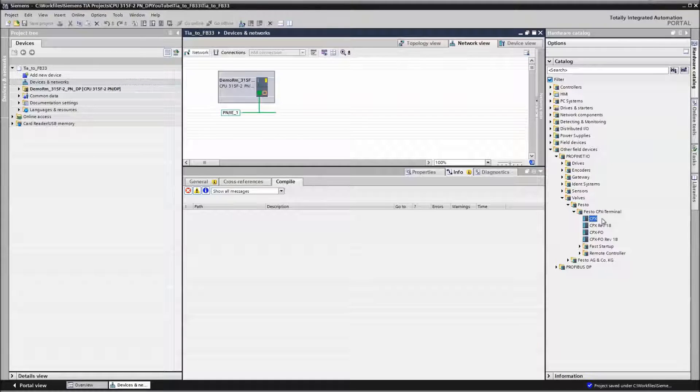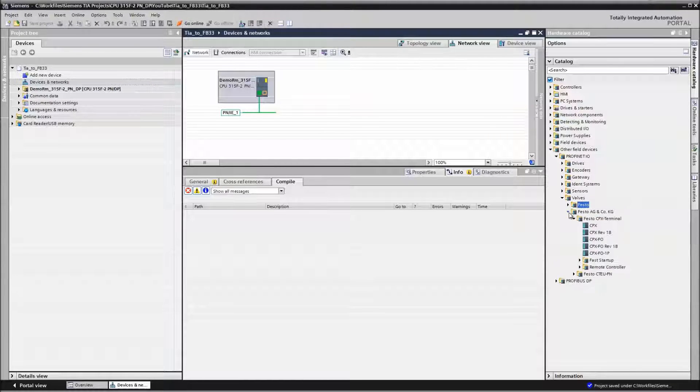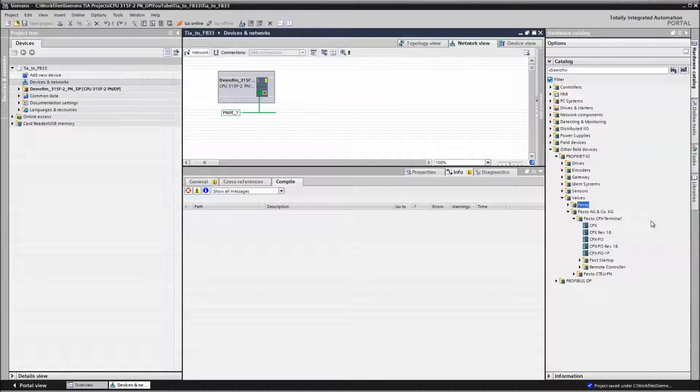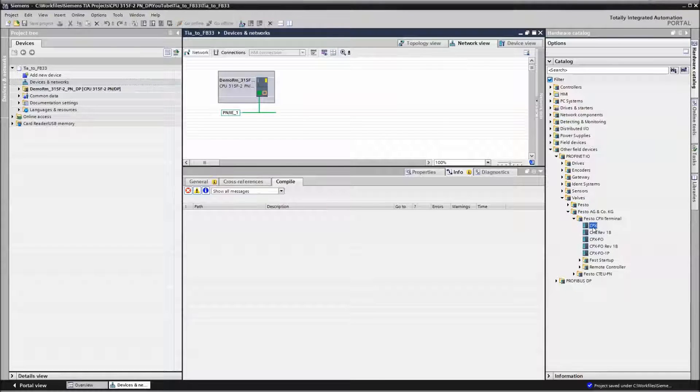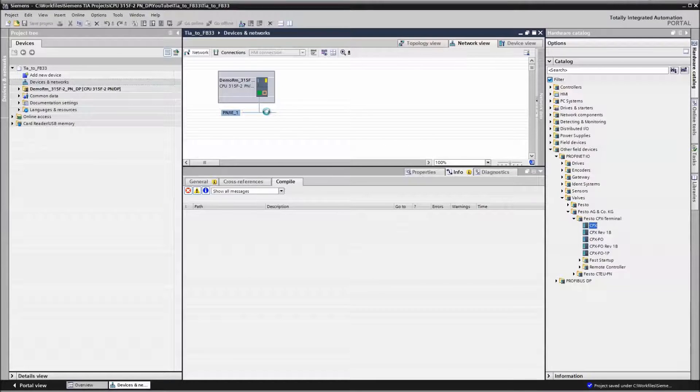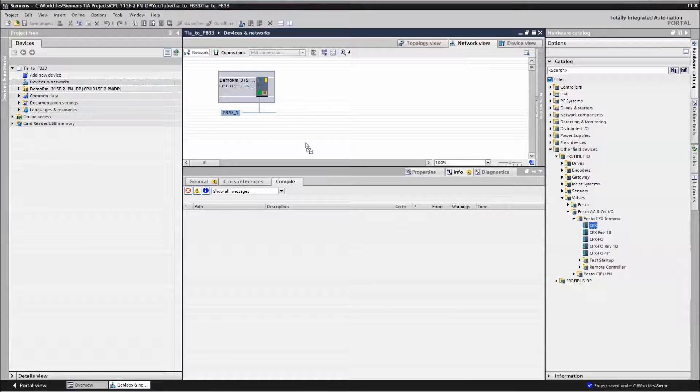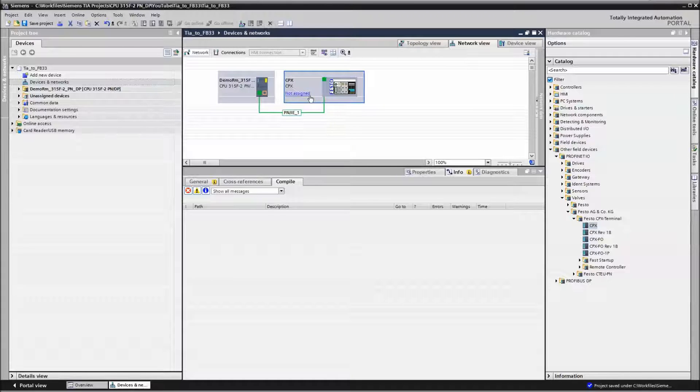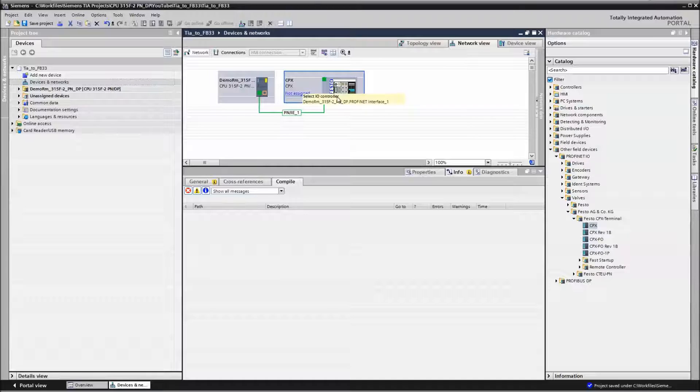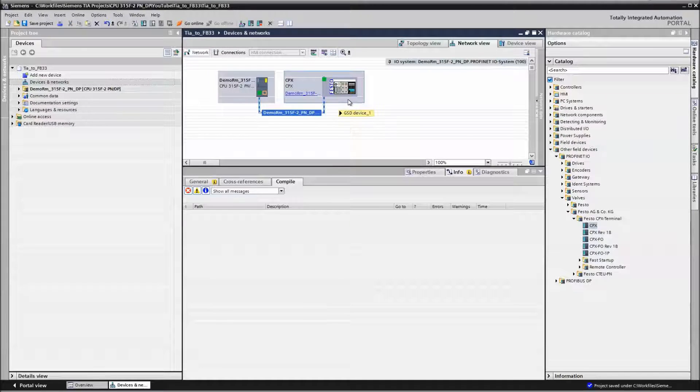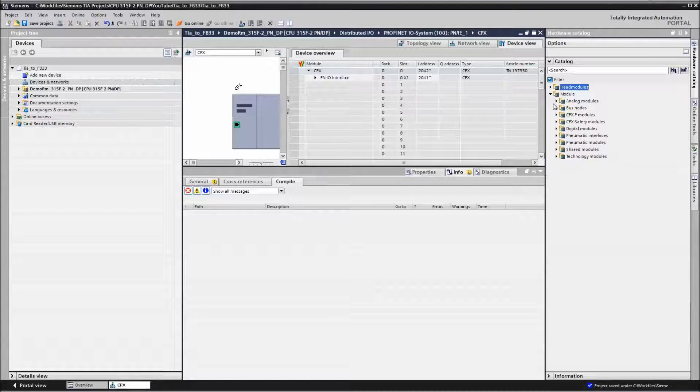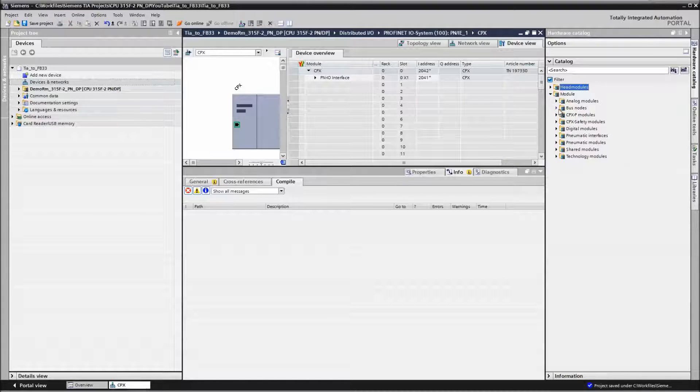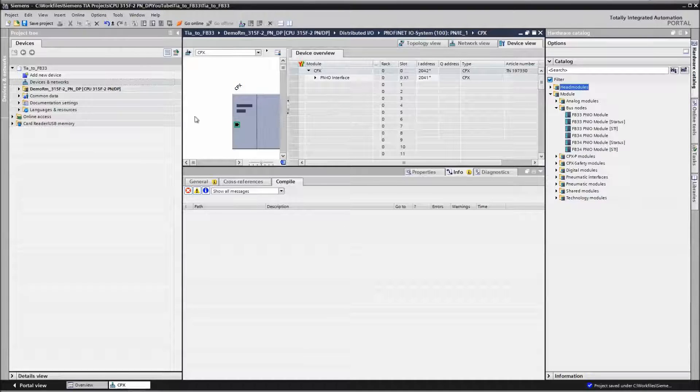And then the first thing we do here is we tunnel down into other fieldbus nodes. So at this point you have the GSD files installed. And now we want to add a CPX. Come over here to our hardware catalog and we drag and drop a CPX onto this network here. And we assign the PLC to that node or to that terminal. And then we double click, go into there.